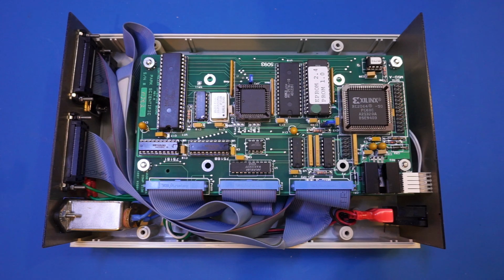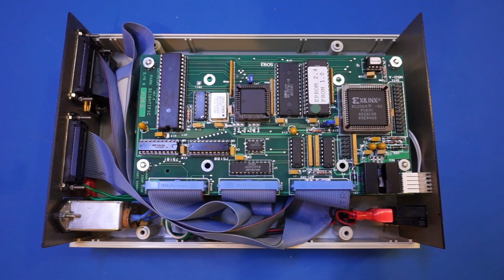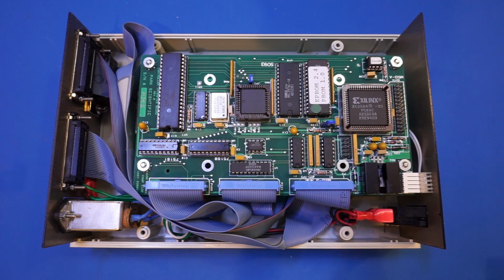And before I forget, the main purpose of this controller unit is to control the stepper motors inside the monochromator and spectrometer so that we can set the starting wavelength, the stopping wavelength, and the scanning speed. It can also control the width of the input and output slits, and so on and so forth.